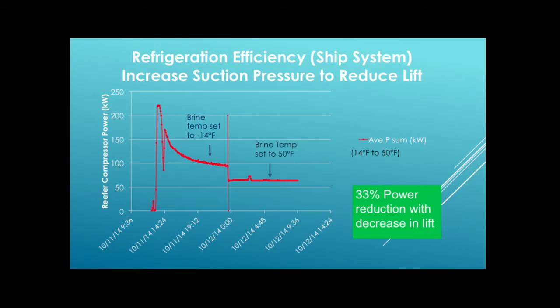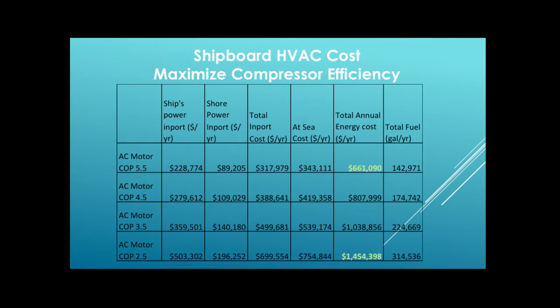This is that lift can go both ways. On some of the ships, we bring up the suction temperature. We've had significant results with that as well. This is on a Military Sealift Command ship, where here's one way of operating it that I saw when I went on the ship and did the retro-commissioning. Here's another way. This is the annual cost for running the AC plant. Just by how you're operating it, it's like $800,000 a year. Same equipment.